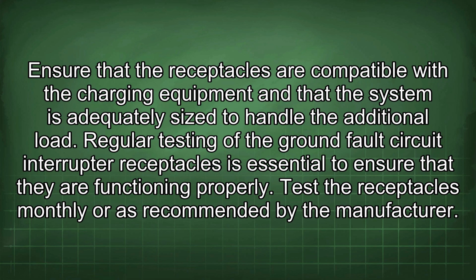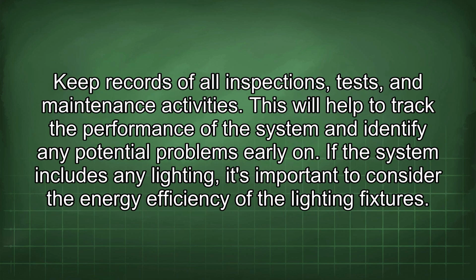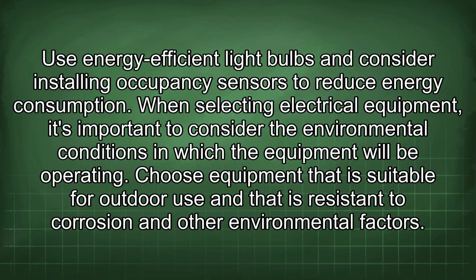Regular testing of the ground fault circuit interrupter receptacles is essential to ensure that they are functioning properly. Test the receptacles monthly or as recommended by the manufacturer. Keep records of all inspections, tests, and maintenance activities. This will help to track the performance of the system and identify any potential problems early on. If the system includes any lighting, it's important to consider the energy efficiency of the lighting fixtures. Use energy-efficient light bulbs and consider installing occupancy sensors to reduce energy consumption.